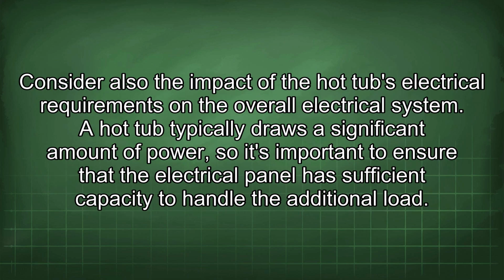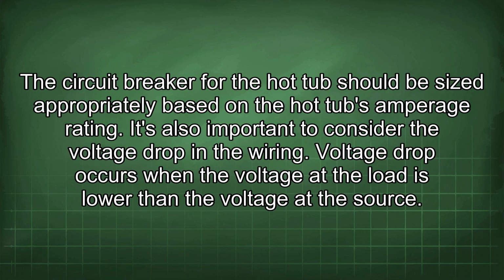Consider also the impact of a hot tub's electrical requirements on the overall electrical system. A hot tub typically draws a significant amount of power, so it's important to ensure that the electrical panel has sufficient capacity to handle the additional load. The circuit breaker for the hot tub should be sized appropriately based on the hot tub's amperage rating. It's also important to consider the voltage drop in the wiring.